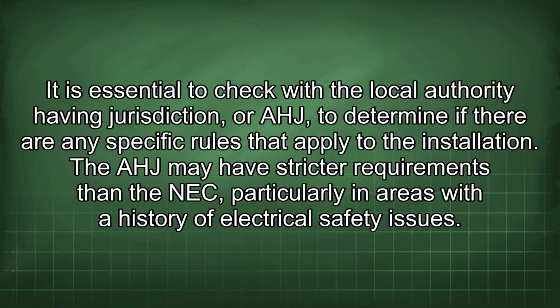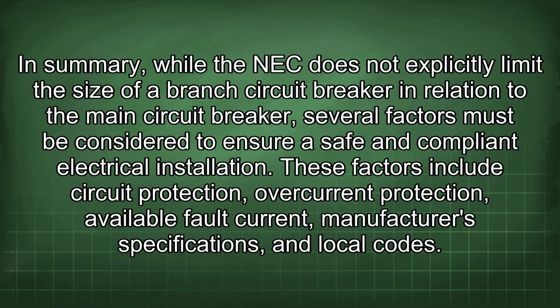The AHJ may have stricter requirements than the NEC, particularly in areas with a history of electrical safety issues. In summary, while the NEC does not explicitly limit the size of a branch circuit breaker in relation to the main circuit breaker, several factors must be considered to ensure a safe and compliant electrical installation. These factors include circuit protection, overcurrent protection, available fault current, manufacturer specifications, and local codes.